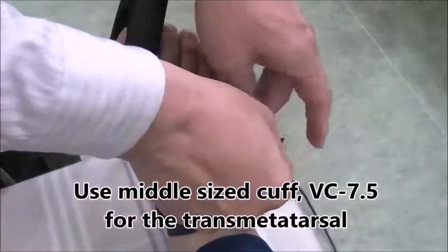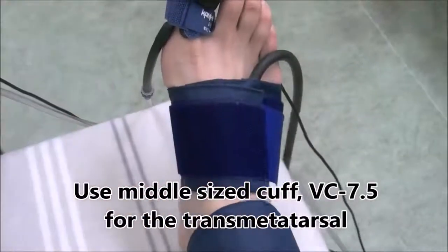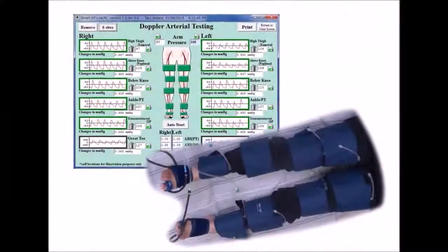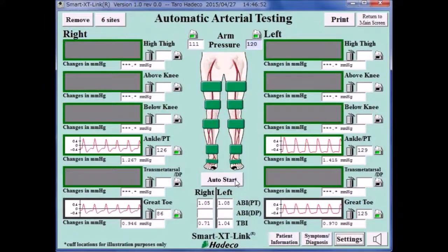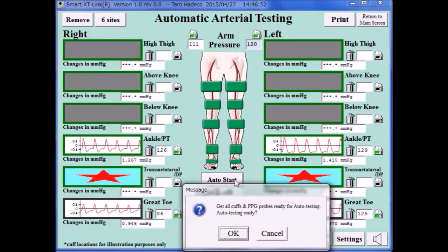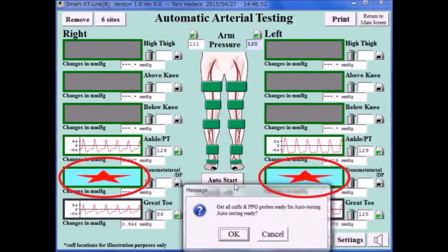Use the mid-sized cuff VC-7.5 for the transmetatarsal testing. Prepare the cuffs, tubing and PPG probes for the testing sites. Click Auto Start. At the beginning of each test, a red star will appear to let you know which site is being tested.